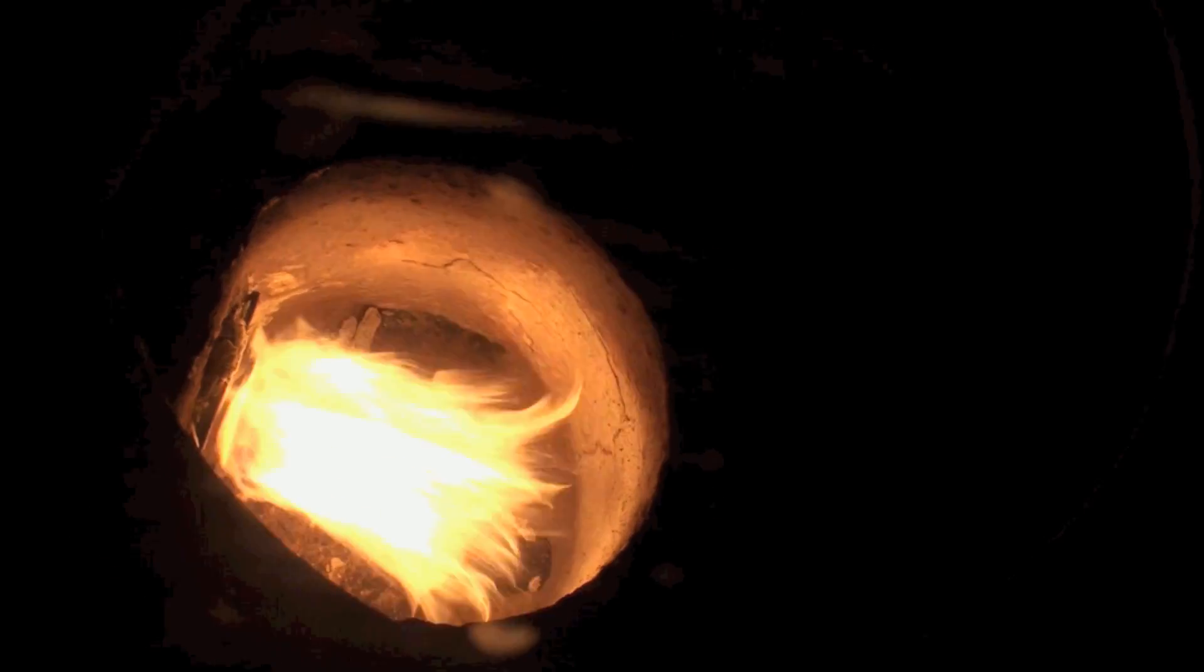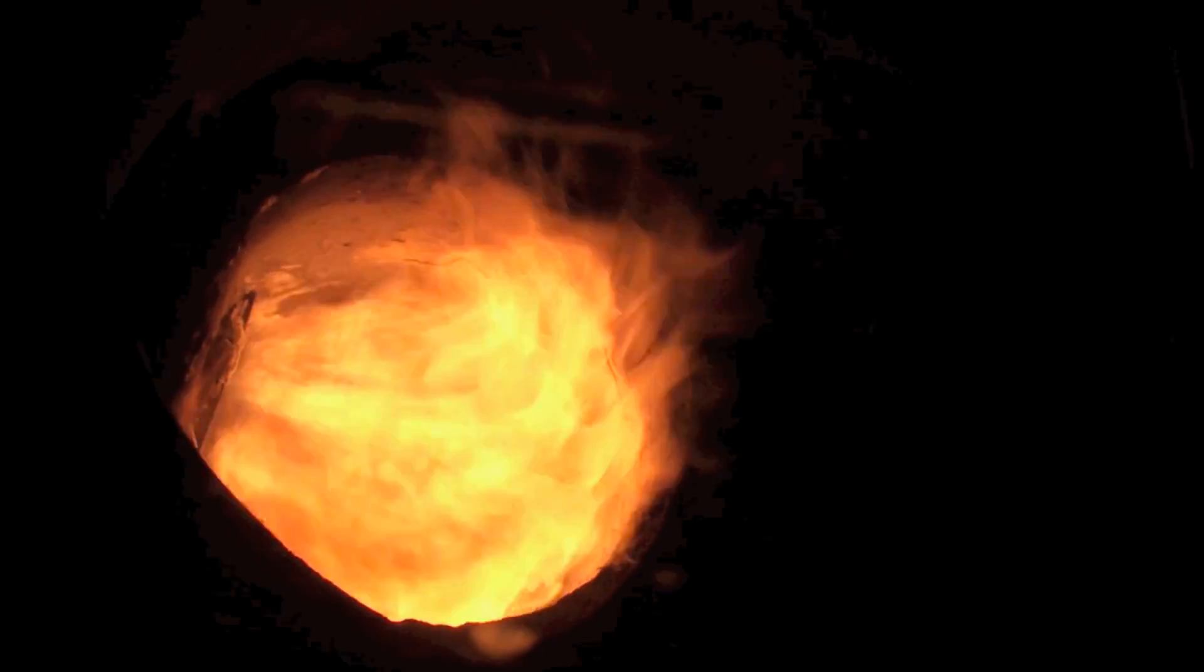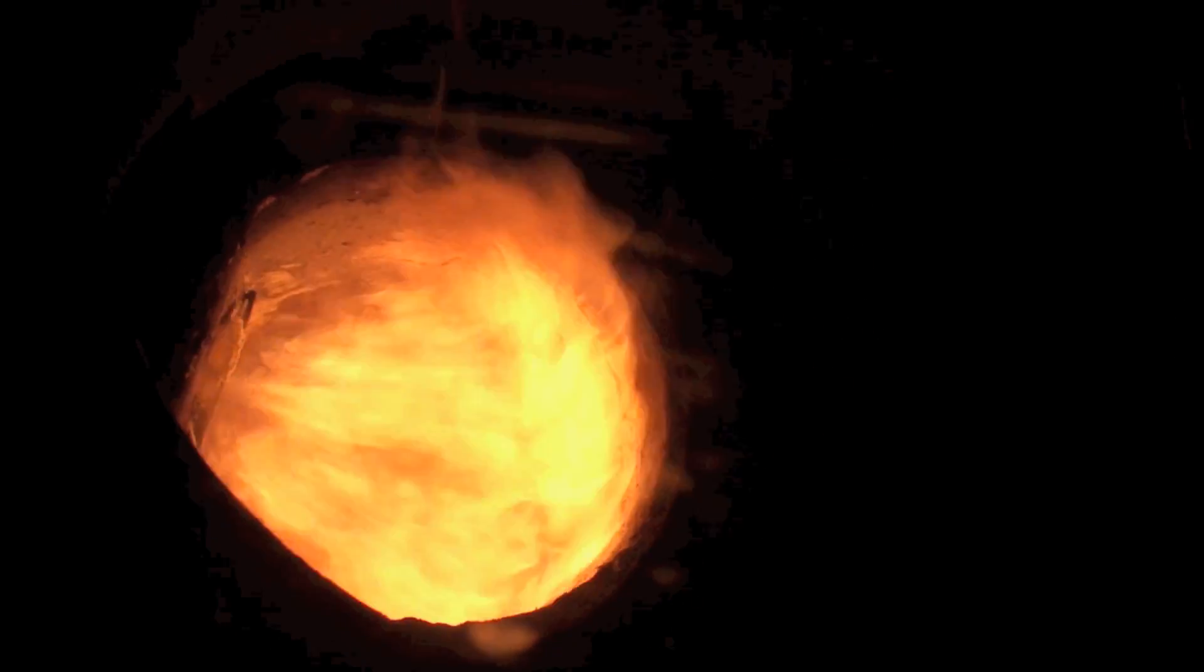But the flame is moving out, curling around a little bit in the back of the combustion chamber. I'm gonna start adding air to her, taking air away from this thing. There you go, see it is actually a darker color.